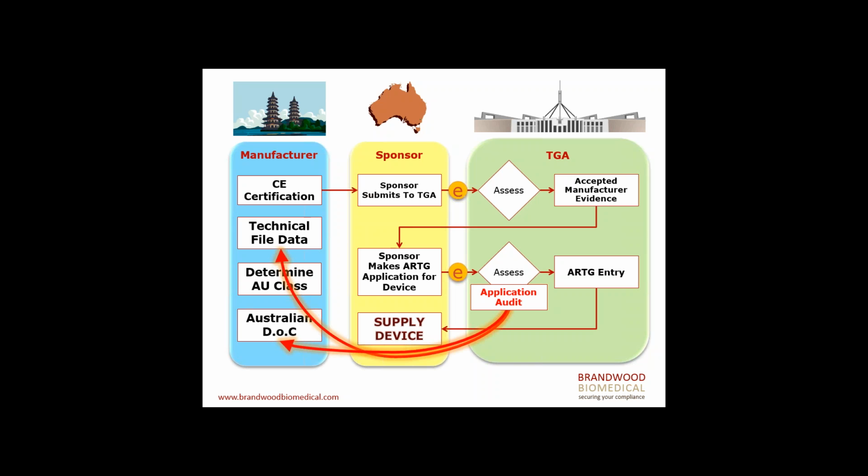So yep, if it's selected for audit, for all other classes, the other documentation requested is an Australian DOC, and the technical file data, as mentioned, it's usually the risk assessment, the clinical evidence, and information supplied with the device, such as IFU and labeling.